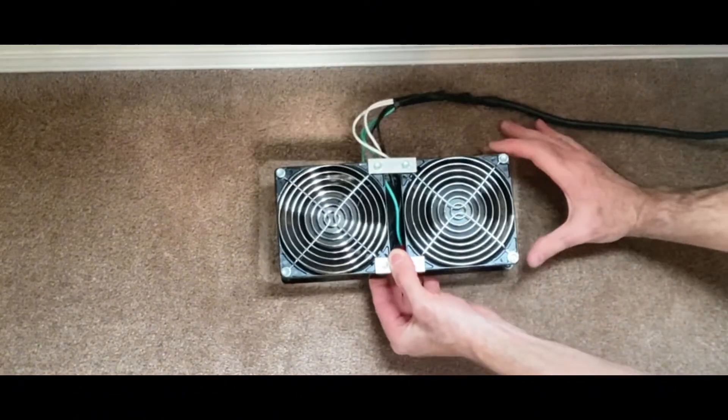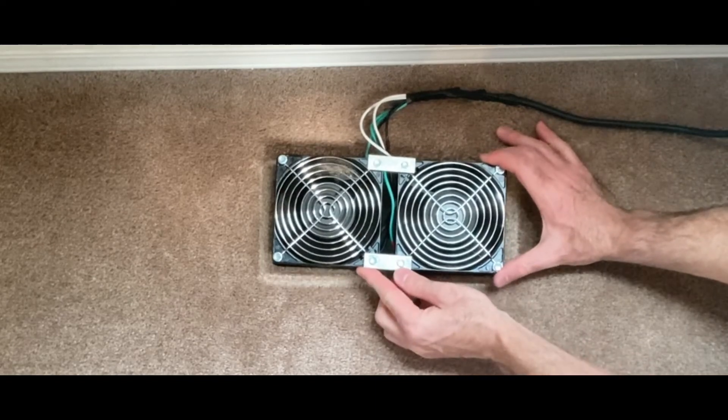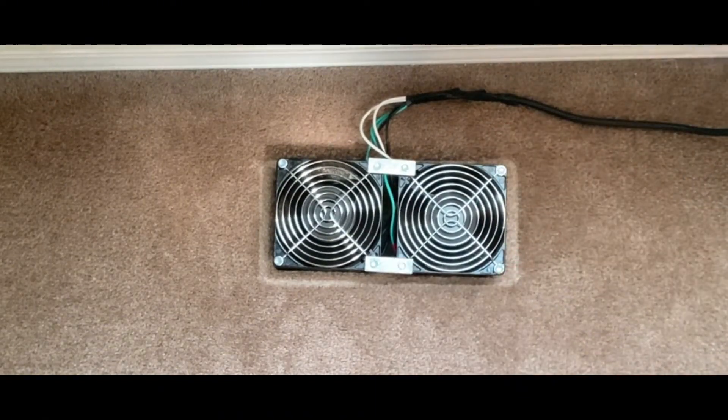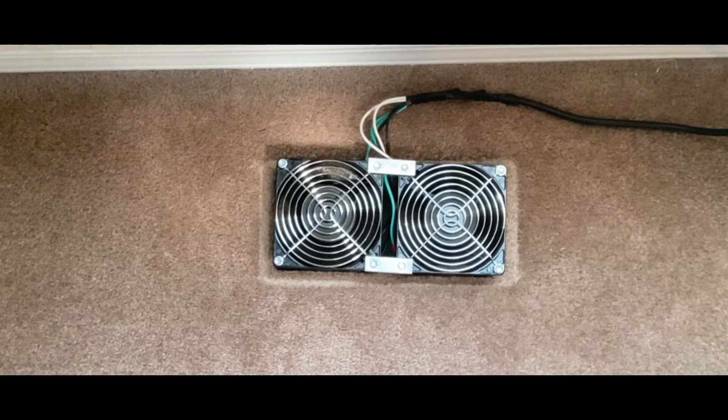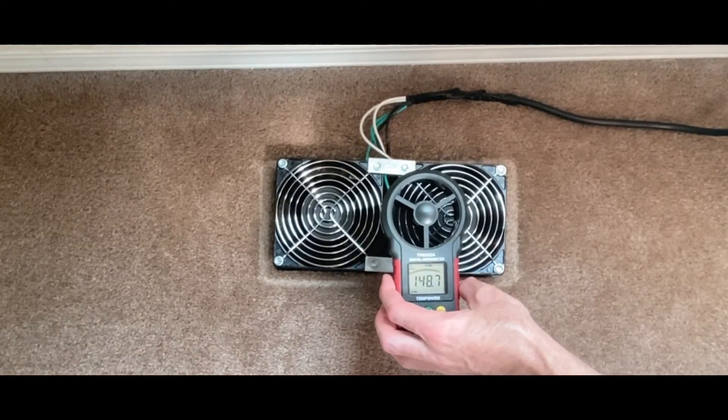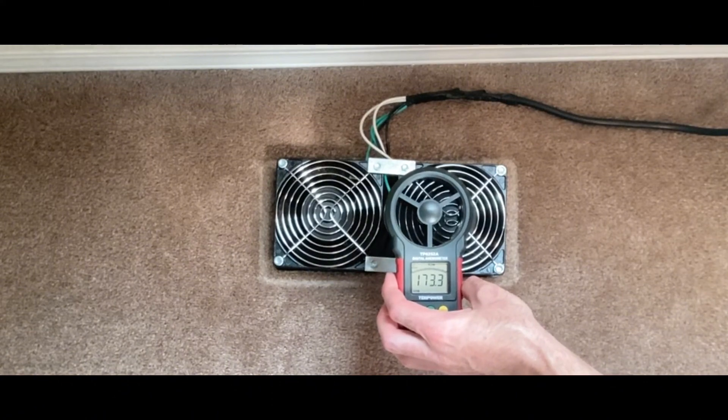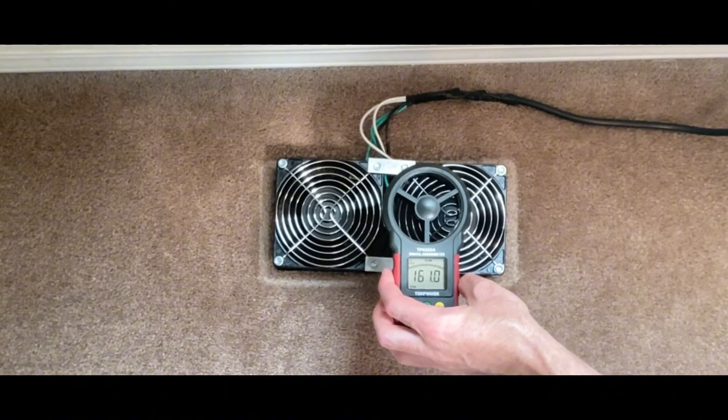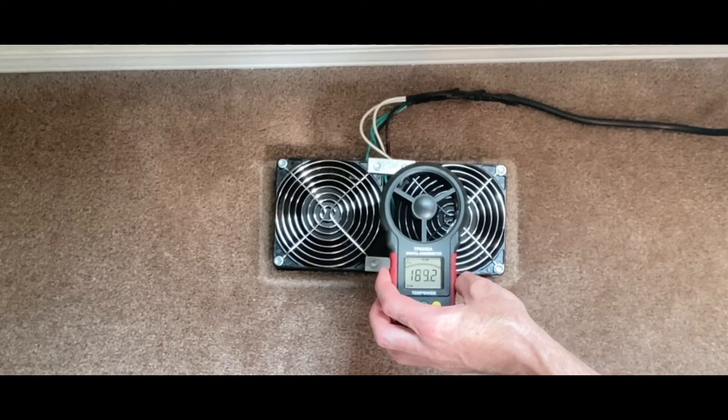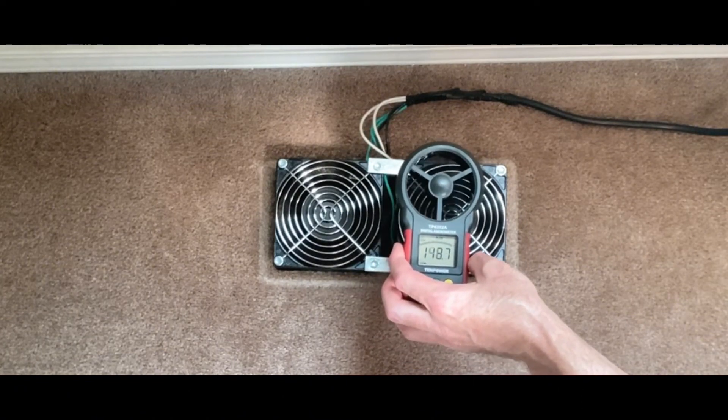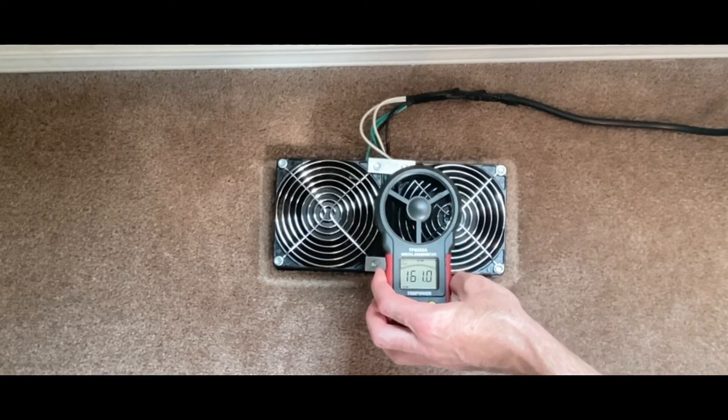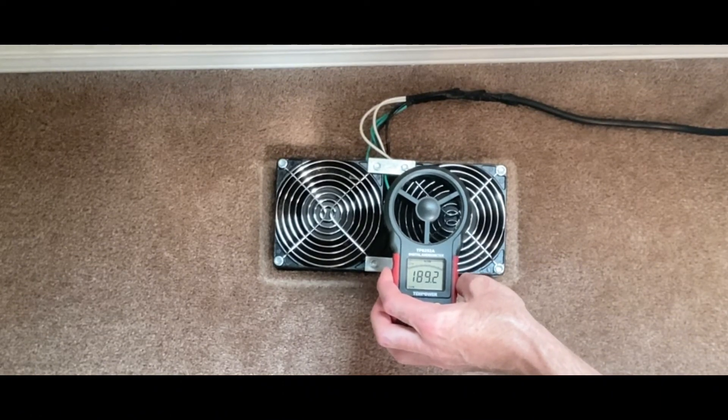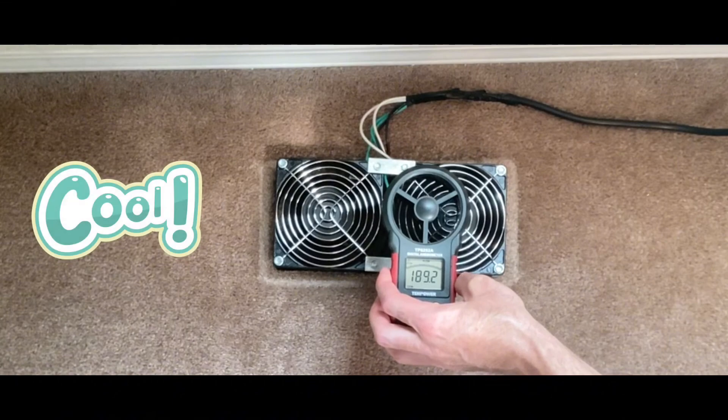Now let's remove the supply register and set the register booster fan directly over the ductwork and see what kind of reading we get. About the same, maxing out at 173, 189.